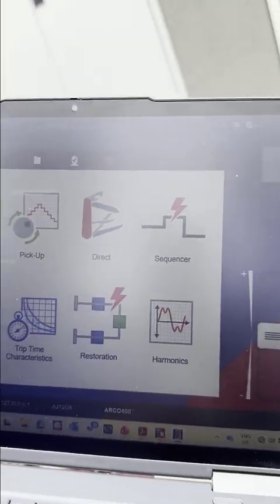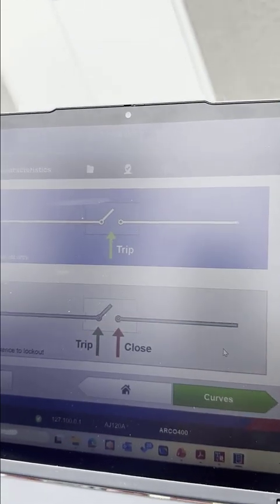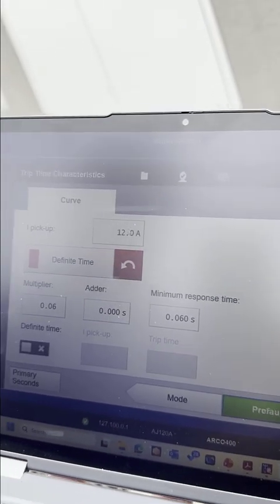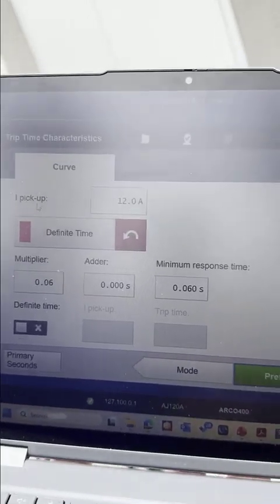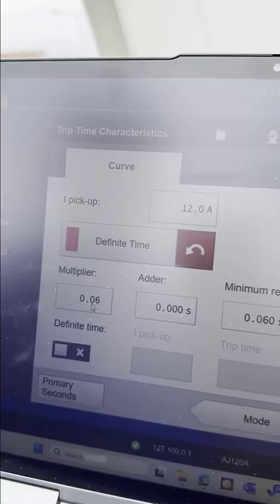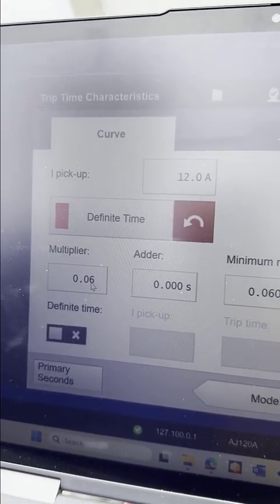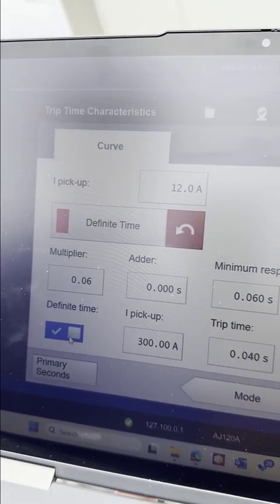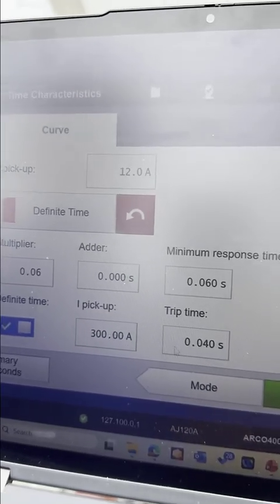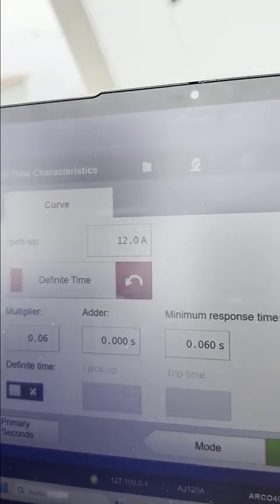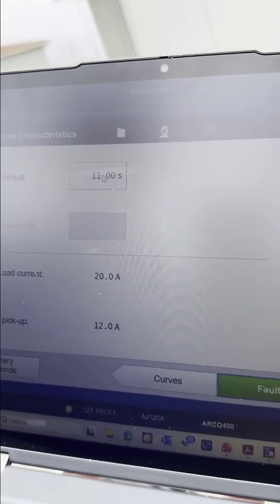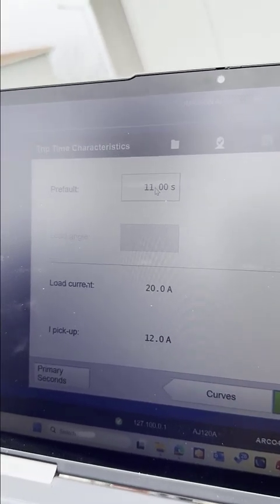Second one, also you can go for the trip time characteristic to check the trip time of different stages, for example the overcurrent stage or the earth fault stage. So we have the pickup value of the earth fault equal to 12 ampere with definite time, and the operating time is 60 millisecond. If you have a second stage, you are free to enter it here as a pickup and the trip time. If you don't, you can disable it, and then you can go for the pre-fault. It's recommended to be longer than the reset time, which is 10 seconds, so we can put it 11 seconds.